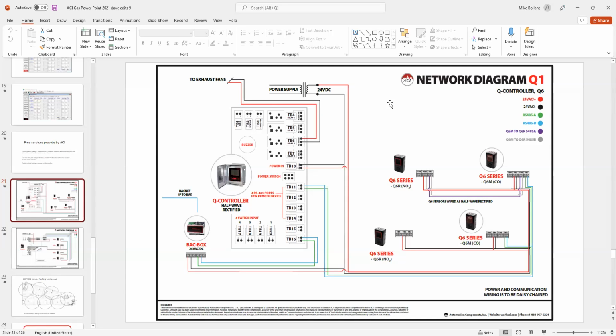So the next screen here is just basically a network diagram, real basic, shows terminal blocks on a Q6, CO, NO2, and coming back to a Q controller. Typically anything over 32 sensors would require the Q controller to do that. And then in this case, there's a BAC Box, which is the BACnet card that needs to be put into the Q controller, and that will give you BACnet to the BAS IP. So if you need to convert that, you'll have to get a converter. Let's leave that up to the contractors.